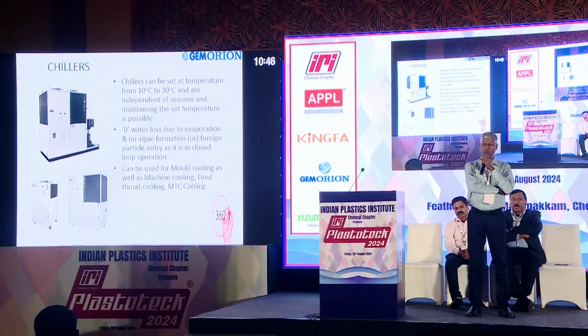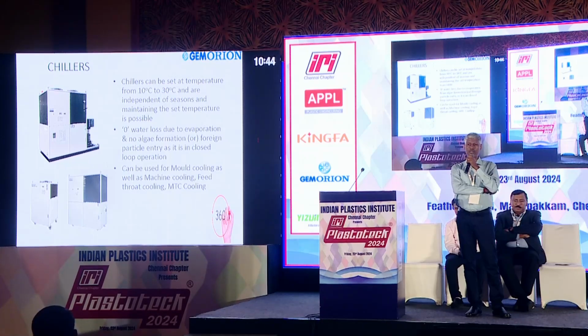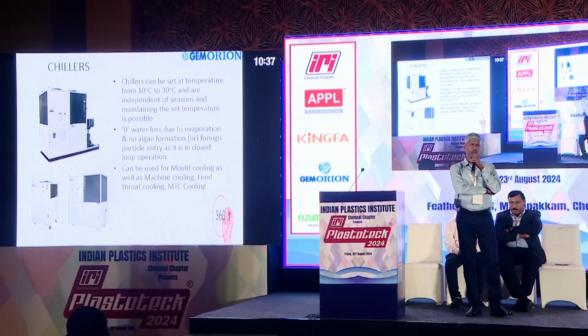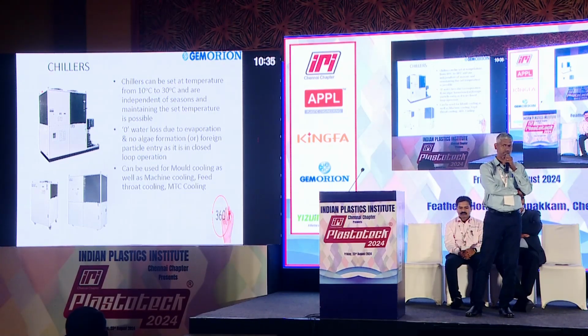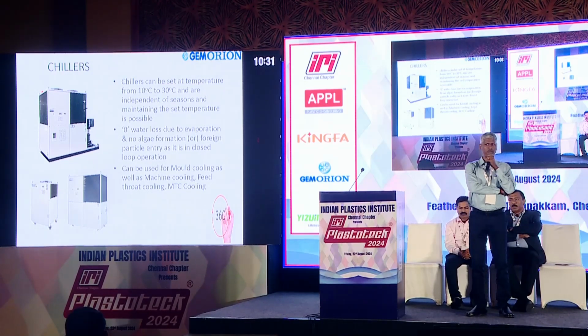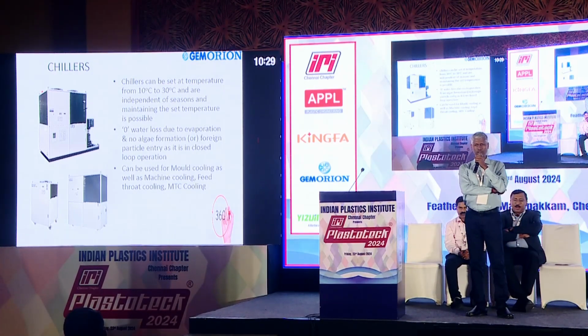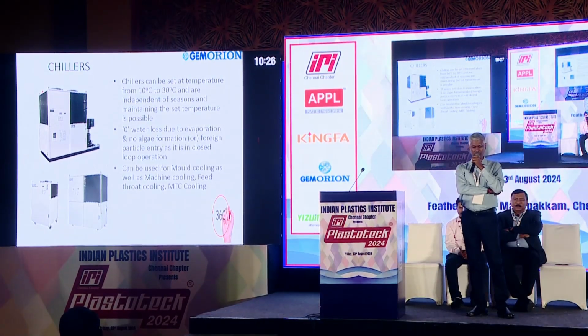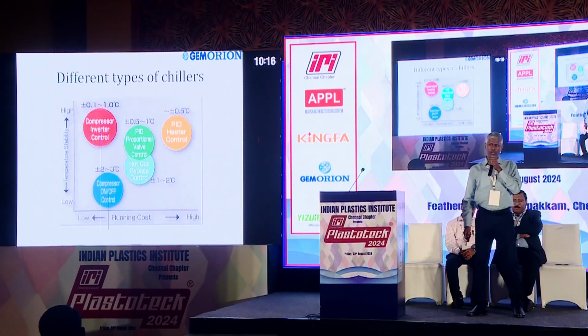So looking at all the possible options, a chiller looks viable. You can set a temperature anywhere between 10 to 30, and this can be maintained across all the seasons. A cooling tower depends on the RH. That means during your monsoon, the cooling tower performance will not be the same as it performs in regular time. Similarly, here there is no water loss, and the chiller can be used for mold, machine, feed throat, as well as MTC cooling. So for chillers, we have many options.